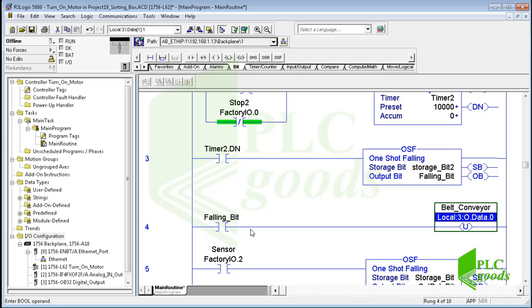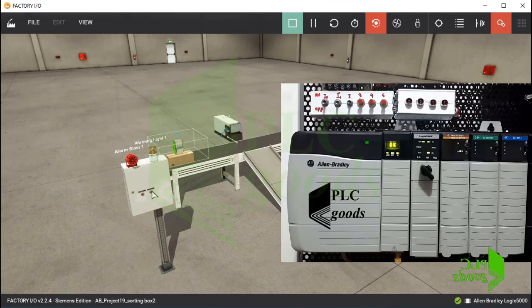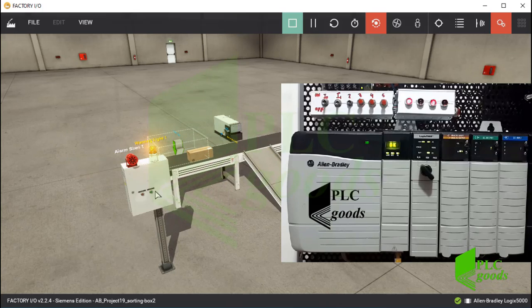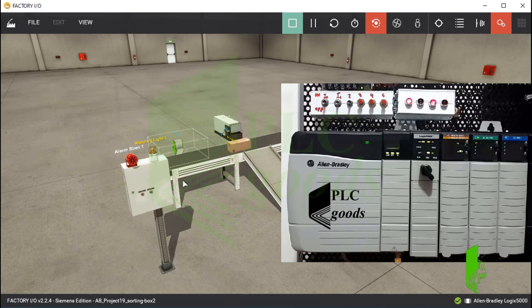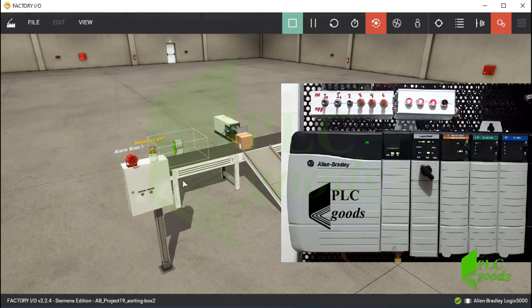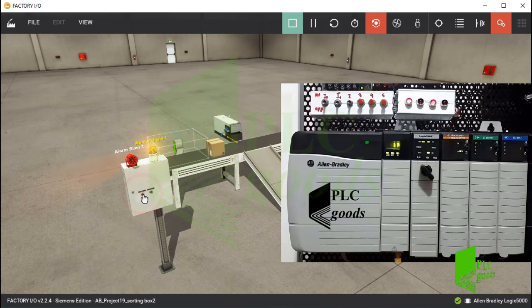Now let me download this program and test it. Now, if I press the stop push button, the belt conveyor will be stopped after 10 seconds.